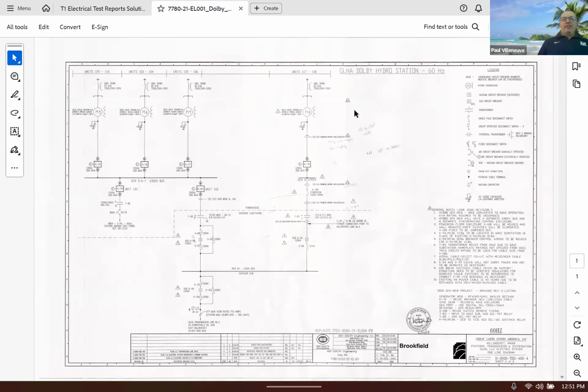And the nice thing is you only have a couple buses, right? There's a bus right here. We'll call that bus 1. If you look over here, there's another bus because there's a transformer, 2, 3, and 4. The only things you need to worry about, I need impedances for that because breakers don't have impedances. These are breakers, right? You can see it's a 1200 amp breaker. That's a no impedance device. So the transformers have impedances and the generators have impedances. And that's it.